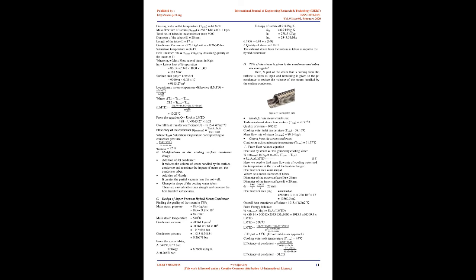V. Design of super vacuum hybrid steam condenser. A hybrid super vacuum steam condenser may be a device with a mixture of jet condensing and surface condensing systems. The exhaust steam at the inlet of the condenser is allowed to split into two streams. One stream of exhaust steam at high velocity and low pressure is diverted into a chamber where mixing occurs with outlet cooling water as shown in Fig. 6. The other stream goes onto the surface of the water cooling tubes of the condenser.